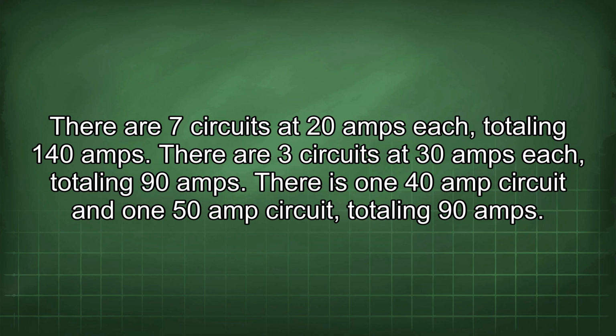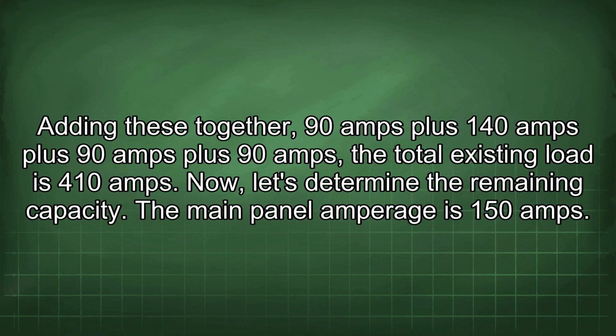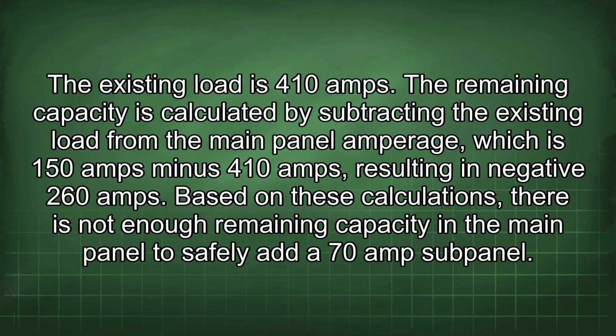There is one 40 amp circuit and one 50 amp circuit, totaling 90 amps. Adding these together, 90 amps plus 140 amps plus 90 amps plus 90 amps, the total existing load is 410 amps. Now, let's determine the remaining capacity. The main panel amperage is 150 amps. The existing load is 410 amps.